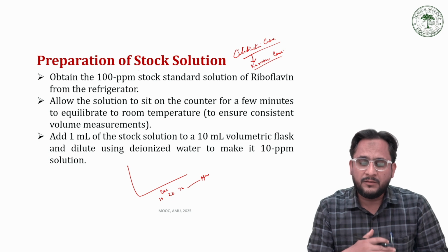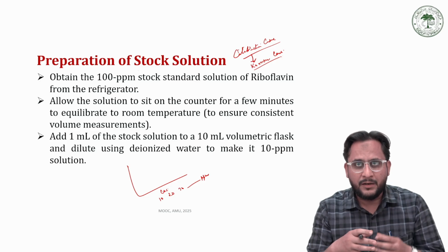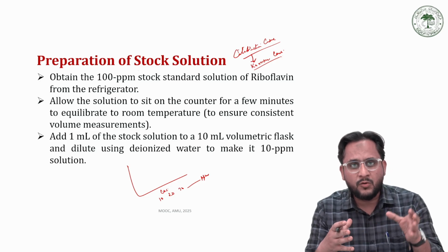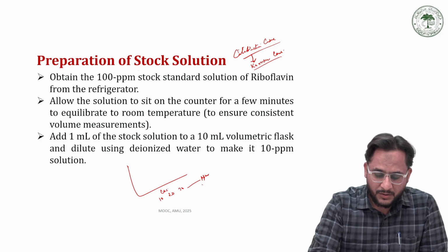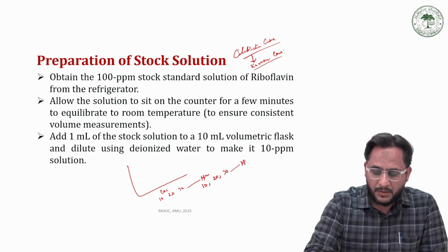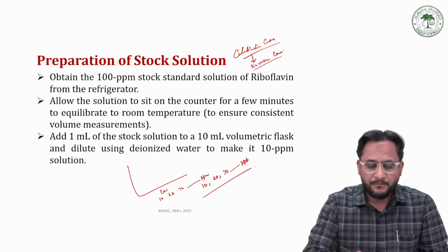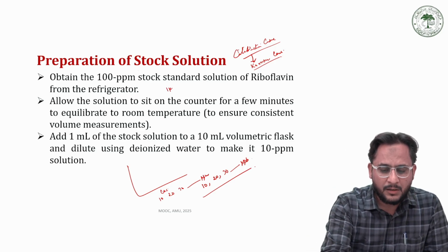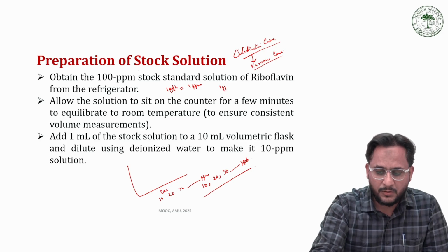And as you all know, with a concentrated sample we have some sort of interferences, so the results may not be reliable, and in order to minimize those interferences, we always go for a dilute solution. So instead of taking 10, 20, 30 ppm for these sensitive instruments, we take 10, 20, 30, and so on, but at the ppb level. We take concentrations for the calibration curve in parts per billion, and 1 ppb is equal to 1 microgram per liter, while ppm is 1000 times more concentrated. 1 ppm is equal to 1 mg per liter.